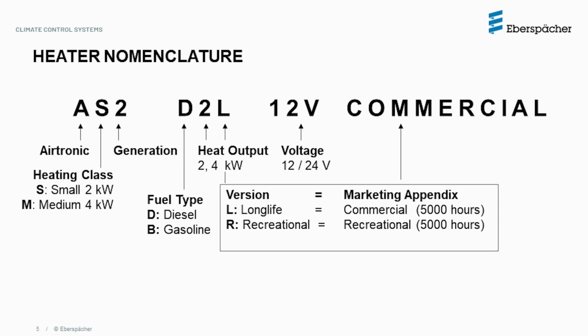This is followed by the fuel type designation of the heater. The letter D designates the diesel version of the heater. The letter B will designate the gasoline version of the heater. The letter B is for benzene, which is a component of gasoline. The number that follows the fuel type will indicate the maximum heat output of the heater. For example, the Airtronic 2 heater with an actual maximum heat output of 2.2 kilowatt is rounded up and designated as a 2 kilowatt heater.